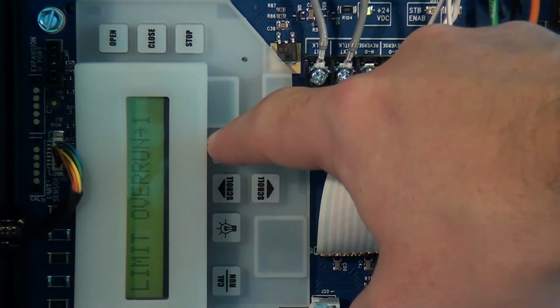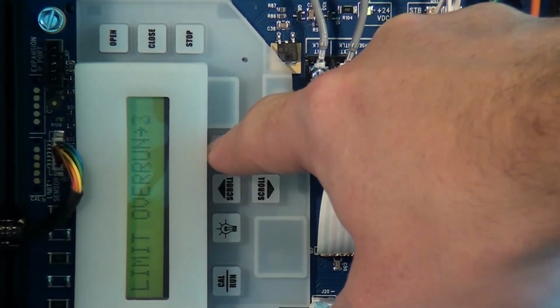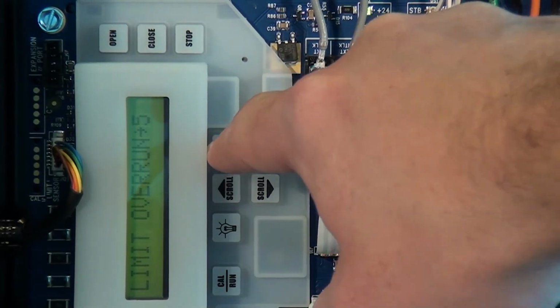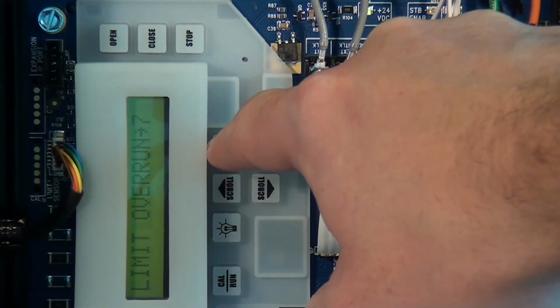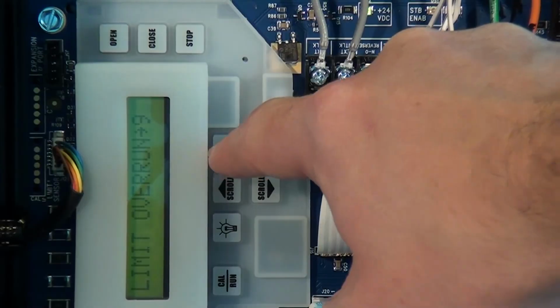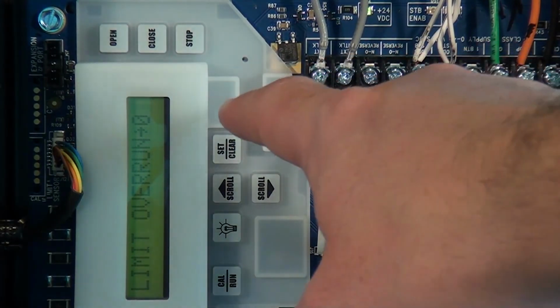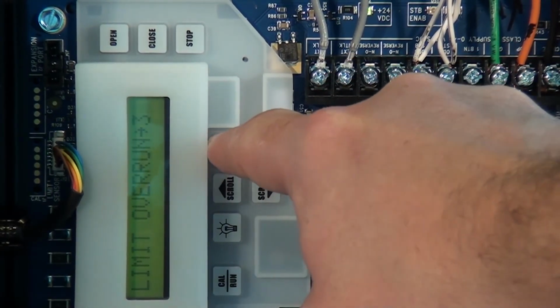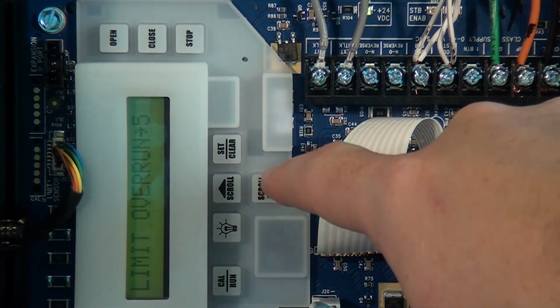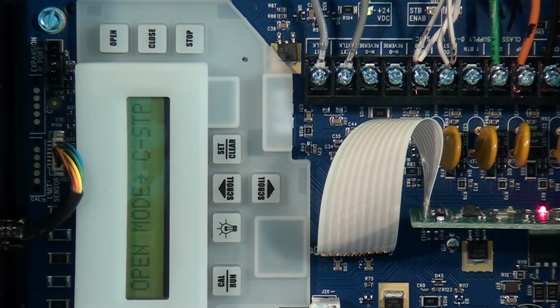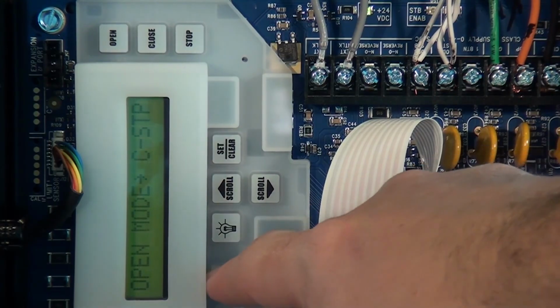Press the Set Clear key to change the value from 0 to 9. 0 will turn off the overrun function and stop the door at the previously set down limit. 9 is the maximum distance the door will travel past the limit. Select the value that allows your commercial door to seal properly. Press either scroll key to lock in the selected value. Press the calibration run key to return to run mode.